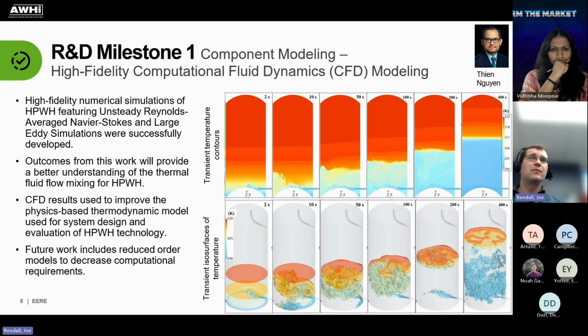In this region up here, which you can say is about 20% of the capacity of the tank when you're getting rid of it, traditional CFD won't get this as good as the LES will for figuring out what the actual temperatures are in that location. So when you're recharging your hot water tank with a heat pump, say going in a different direction, you pull the water in a different direction. When this water gets to your heat pump, you get really different COPs.